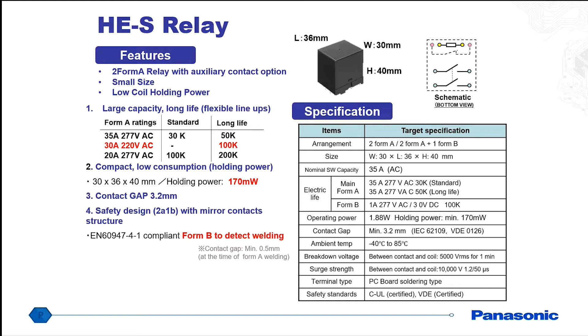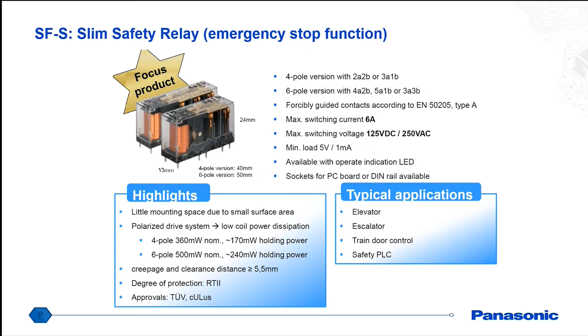Here's another type of relay that we are also recommending for autonomous guided vehicles, and this is a slim type safety relay. These use mechanically linked contacts, similar to the previous slide, where it's got several normally open contacts as well as normally closed contact configurations that are linked together. So if you do have any kind of welding, this would be able to very quickly detect it without any additional circuitry. This is a nice, very small, slim type size, as well as very low power consumption, down to 170 milliwatts holding power.